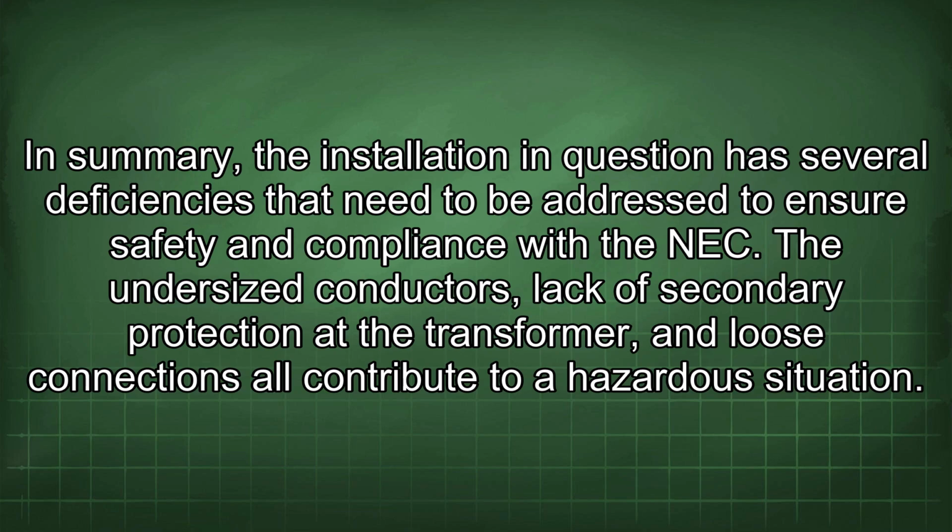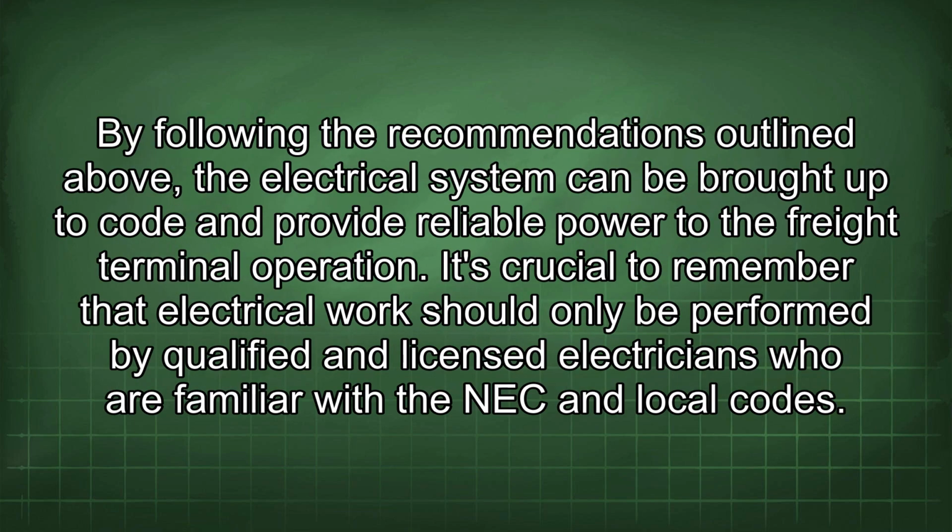The undersized conductors, lack of secondary protection at the transformer, and loose connections all contribute to a hazardous situation. By following the recommendations outlined above, the electrical system can be brought up to code and provide reliable power to the freight terminal operation. It's crucial to remember that electrical work should only be performed by qualified and licensed electricians who are familiar with the NEC and local codes.